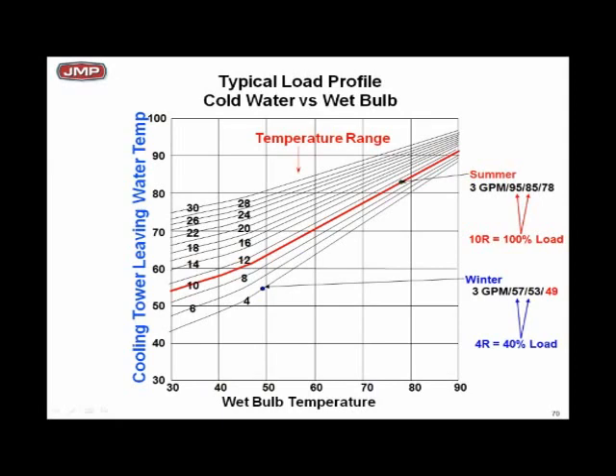Let's look at what happens to a wet bulb situation on a cooling tower. Let's see what's going on here. So I'm trying to make what? 85, 95 degree water. Go to a summer condition. I want to make 85 degree cold water with 78 degree wet bulb. And my range is going to be 85 to 95, and I got a full load. All right, so if I'm making 85 degree water at 78 degree wet bulb, then my approach is 7 degrees. 78 degree wet bulb, I'm making 85 degree water, 7 degree approach.